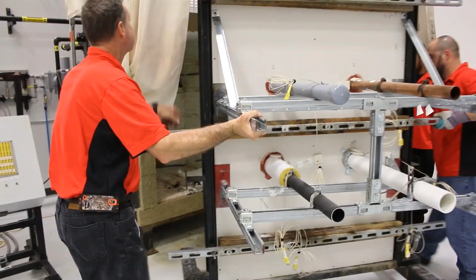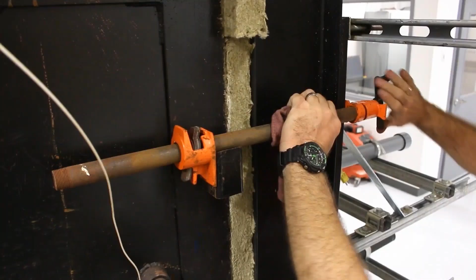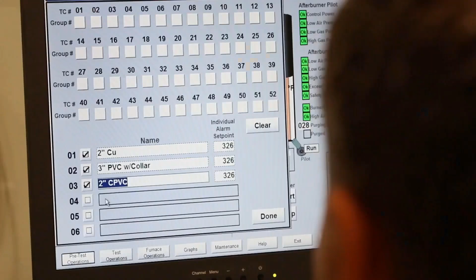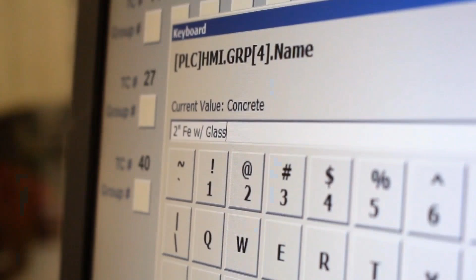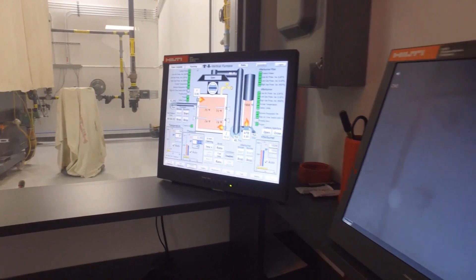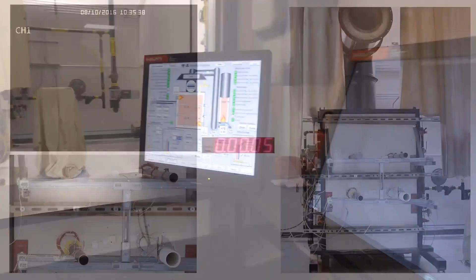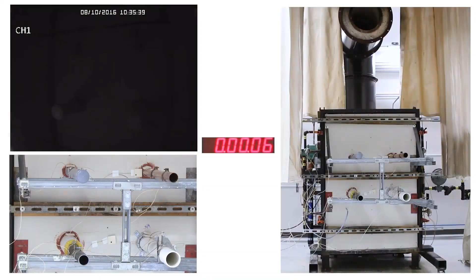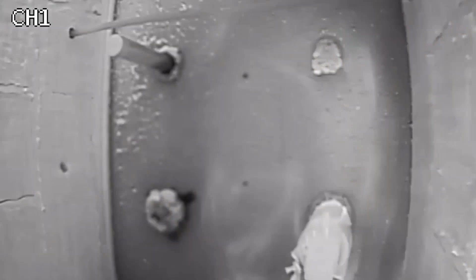When it's ready, the assembly is carefully secured to the furnace. Lead wires from the thermocouples are attached to the monitoring system and tracked with our computer program. With a mouse click, the furnace's burners are ignited and the test begins. In a few minutes, the PVC pipes and insulation on the fire side of the wall melt away, causing them to ventilate smoke into the room. Heat causes graphite in the product to expand, creating a seal that continuously expands as long as the heat is applied. This closes the pipe and limits the passage of smoke and harmful gases into other parts of the building.